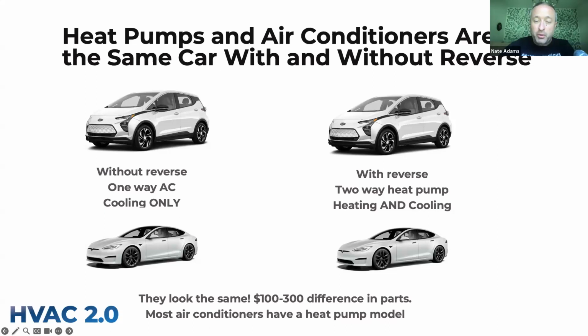Basically, heat pumps just have a couple of extra parts. One is called the reversing valve, which lets the refrigerant flow either way, so that's like adding the reverse gear. And then it needs a defrost board, which determines when the outdoor unit is turning into a literal block of ice and tells it to defrost itself.